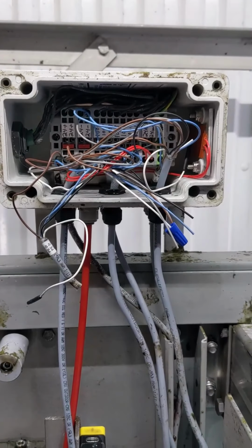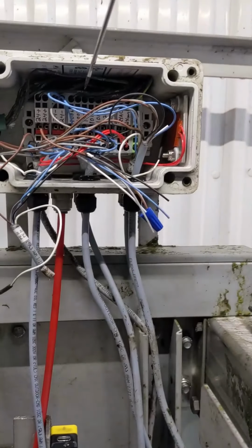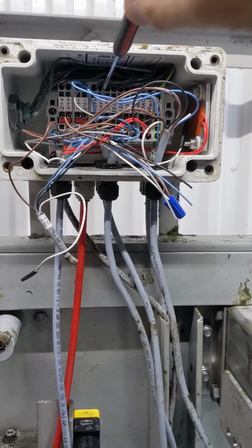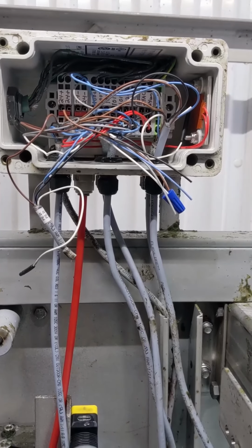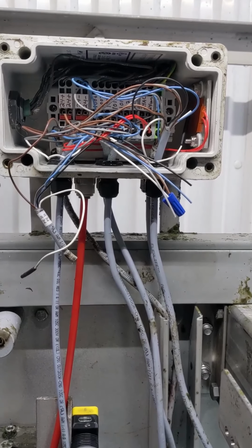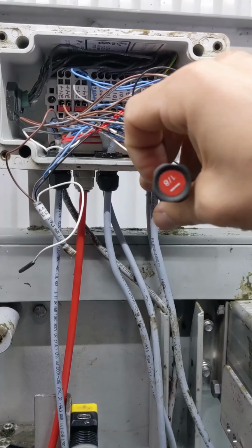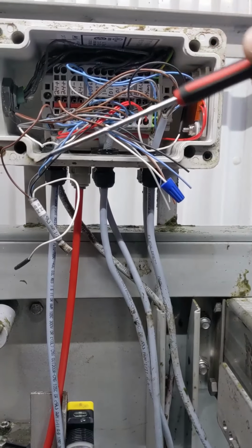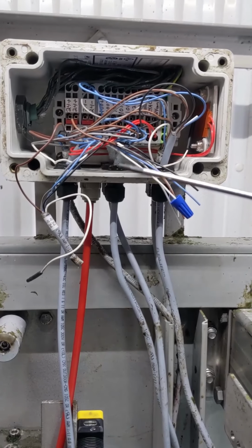Okay, so you may already know this, but if you don't, these are Wago terminals, okay? They're Wago blocks. Now, typically, you'd use a Wago stick. I don't have one, but you can use the 1/8 inch Milwaukee screwdriver. It's basically shaped exactly the same. So really, you just want something flat like this that'll go in there, and basically there's just a spring-loaded piece of metal in there that's gonna bite into our wire to give us the connection that we want.